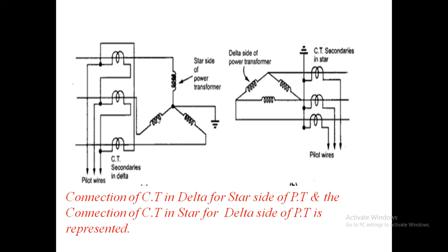So here, with an internal fault in the power transformer winding, the balance in the CT gets disturbed. The operating coil carries current which is proportional to the difference of current between the two sides of the power transformer. So the relay operates and trips the main circuit breaker on both sides of the power transformer. The main point is it gives protection against short circuit faults between the turns, that is, turn faults. The turns ratio of the power transformer gets affected, due to which the current on both sides of the transformer becomes unbalanced.